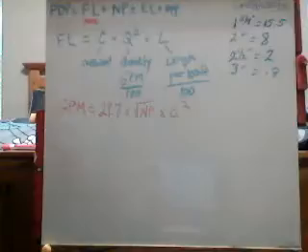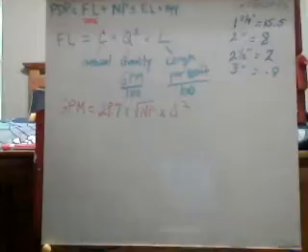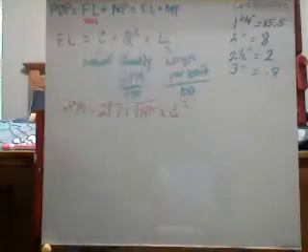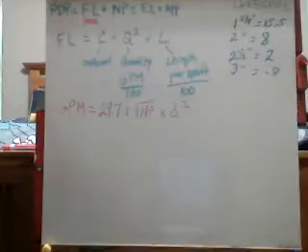The next thing we're going to start is, it's pretty easy when you have a fixed stream like a fog nozzle, and we know that it's 150 gallons per minute. But what happens if we have a smooth bore? This is really where, for paper and test purposes, the equation becomes much more cumbersome, because before you can get to the Q, you have to figure out what you can actually flow. The next formula you need to know is the GPM formula: 29.7 times the square root of the nozzle pressure times diameter squared.